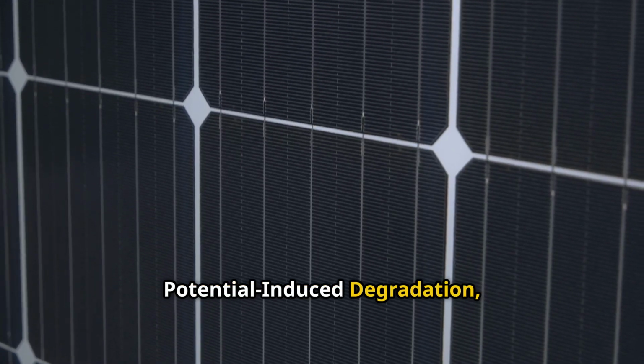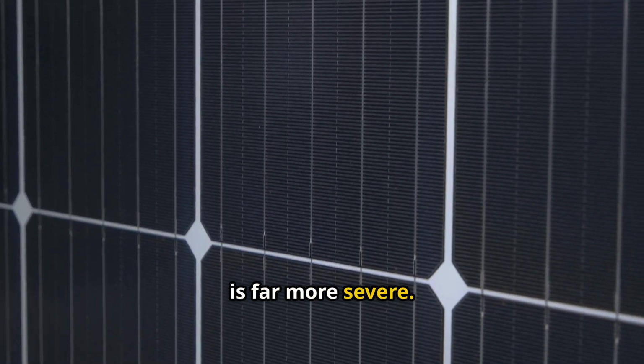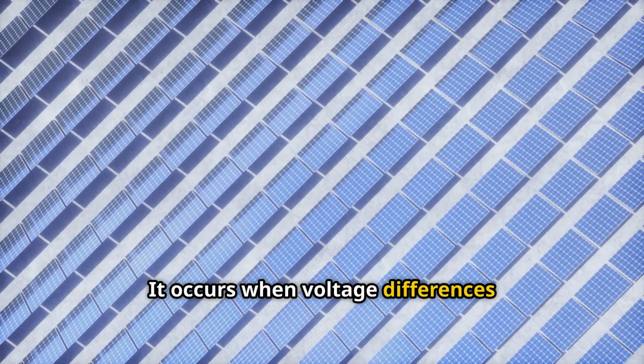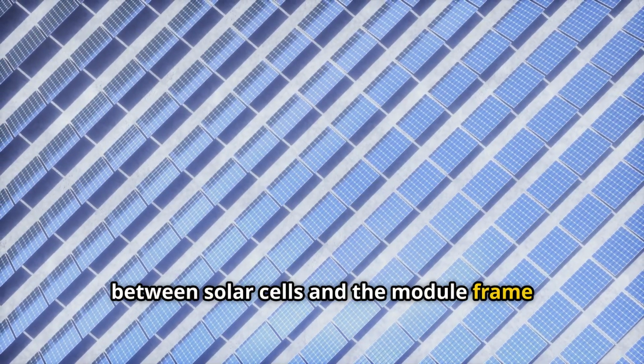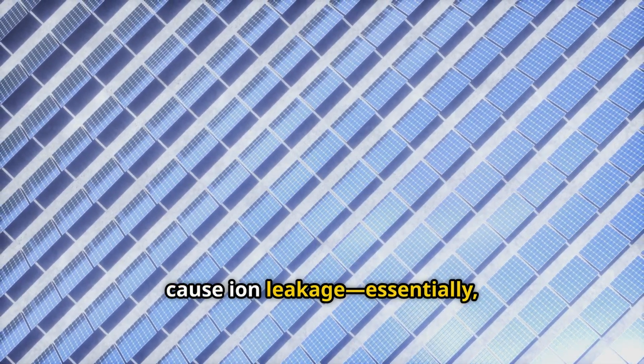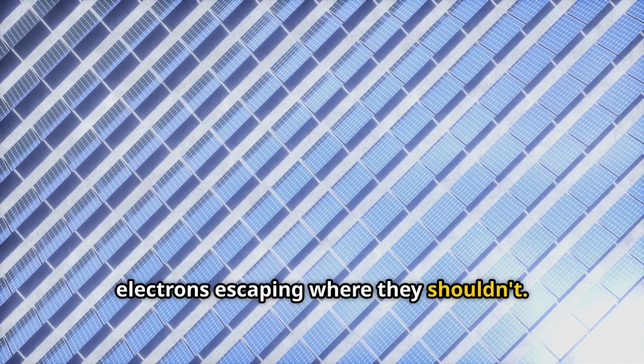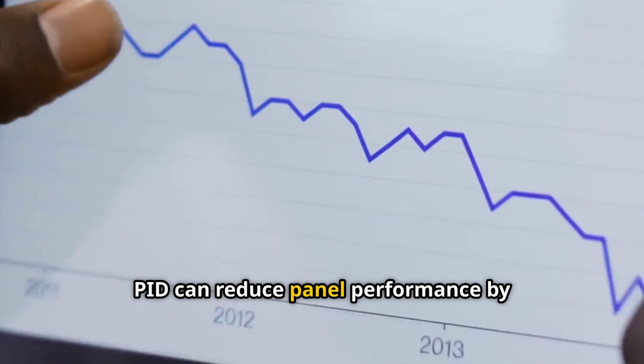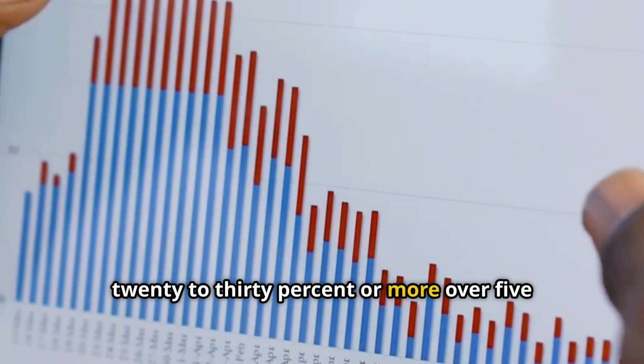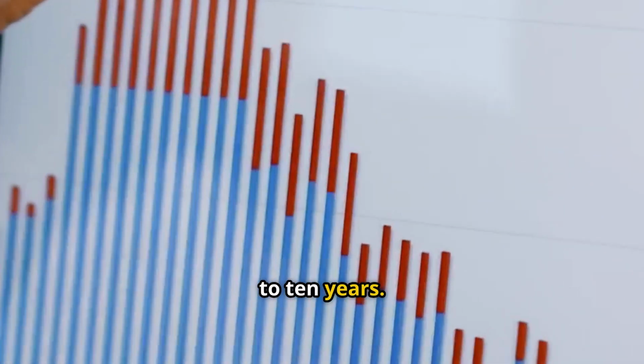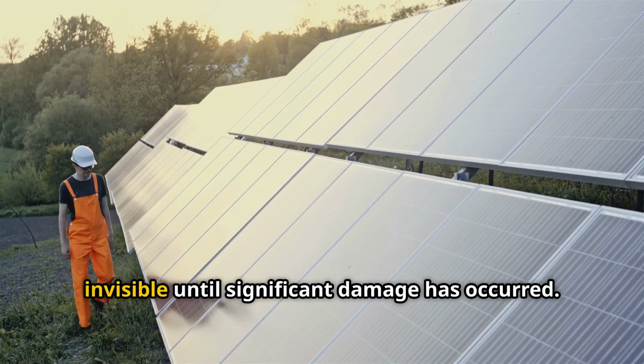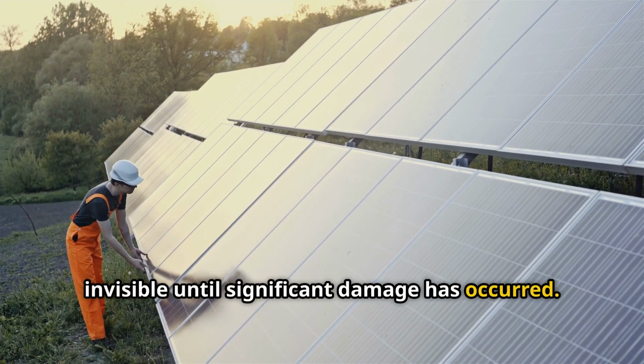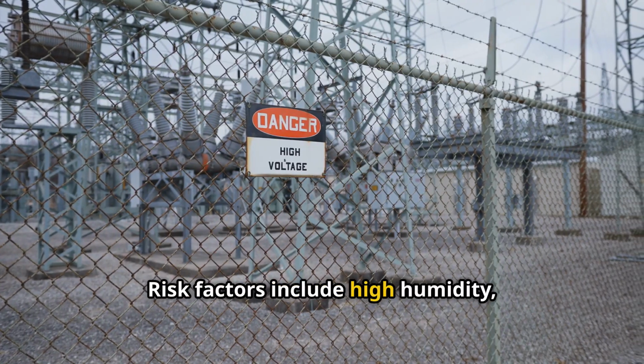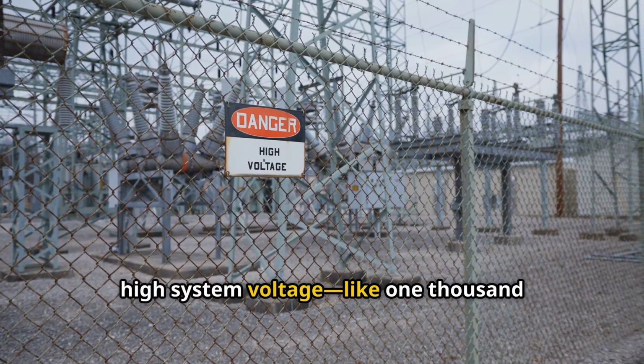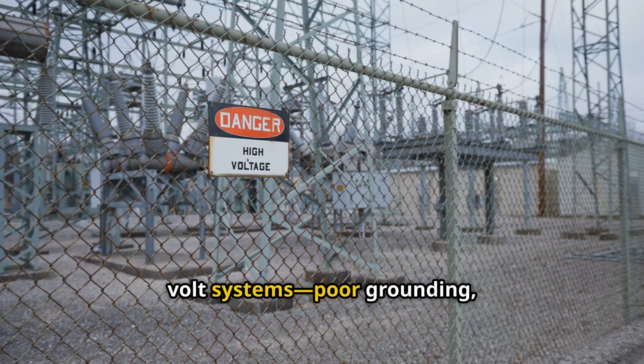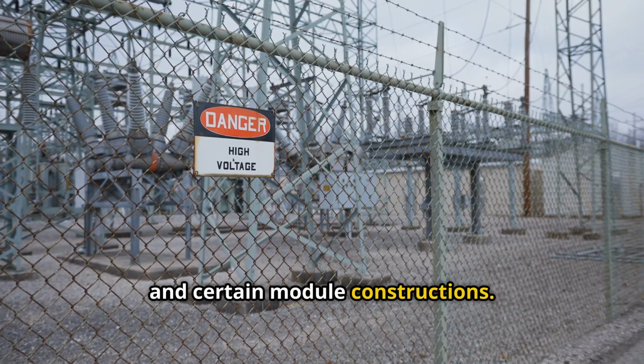Potential induced degradation, or PID, is far more severe. It occurs when voltage differences between solar cells and the module frame cause ion leakage, essentially electrons escaping where they shouldn't. PID can reduce panel performance by 20 to 30% or more over 5 to 10 years. The worst part is that it's often invisible until significant damage has occurred. Risk factors include high humidity, high system voltage, like 1000-volt systems, poor grounding, and certain module constructions.